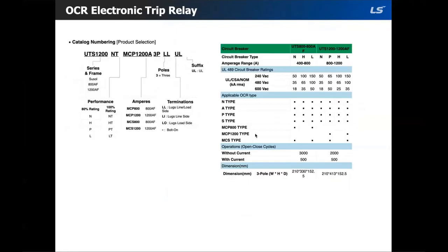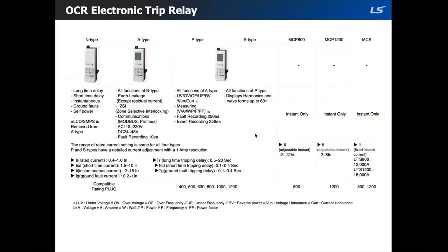So the OCR electronic trip relays provide additional protection. It supports advanced measurement functions for voltage, current, power, electric energy, harmonics, and communication. They are only available on the UTS 800 and 1200 MCCBs. They offer additional protection functions such as overcurrent, short circuit, and ground fault. So there are 4 types of OCRs: N-type, A-type, P-type, and finally the S-type. All OCRs have long time delay, short time delay, and instantaneous trip functions.